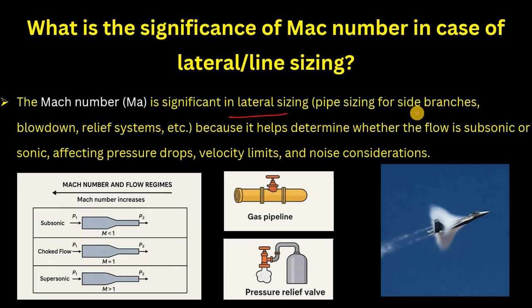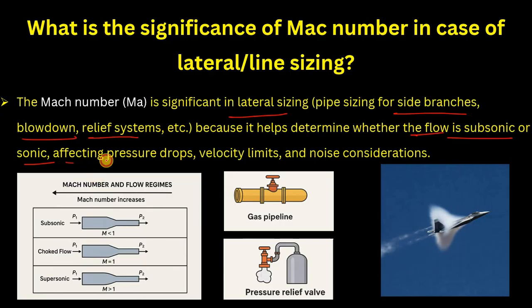The significance of Mach number in lateral or line sizing is that it tells us whether your flow is subsonic, sonic, or supersonic based on whether Mach number is less than, equal to, or greater than one. It affects pressure drops, velocity limits, and noise considerations — all very important during lateral sizing, because exceeding velocity or noise limits can lead to mechanical failure and an unstable design.